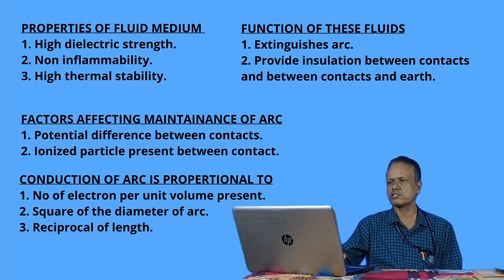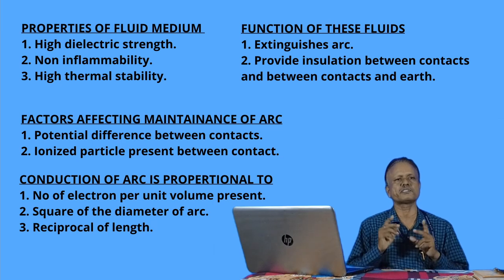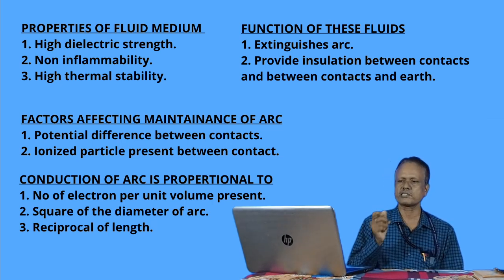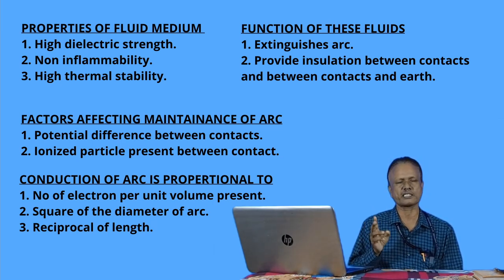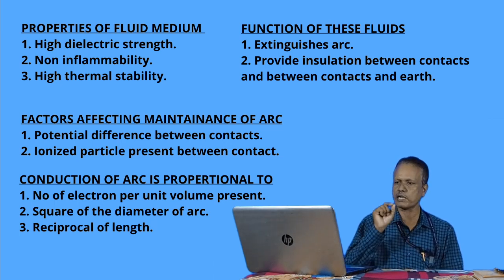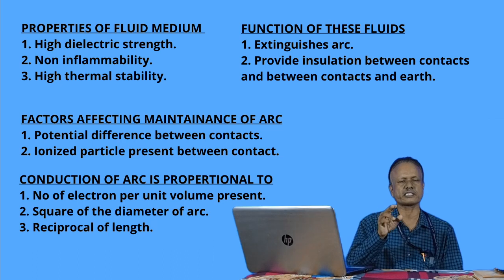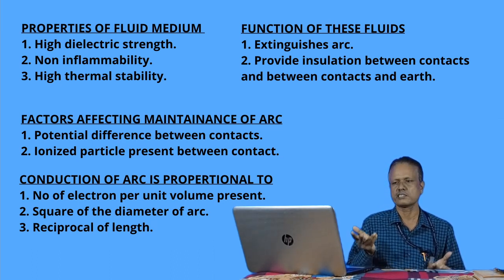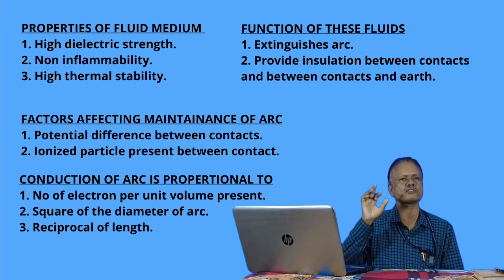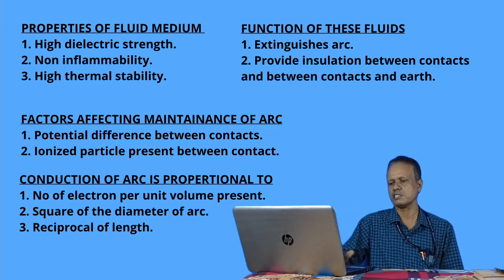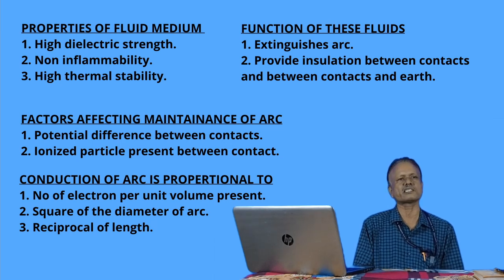Next, the functions of these fluids. If we go to the functions of the fluids, we will observe that there are 2 functions. First of all, extinction of the arc. Second is to provide insulation between the contacts and the earth. So this is very clear to everyone that these 2 functions are the functions of the fluid used inside the circuit breaker. Then next, factors affecting the maintenance of the arc.